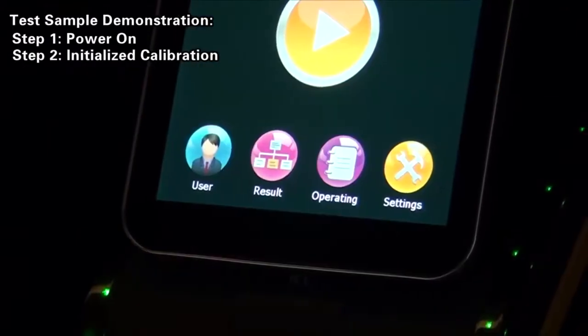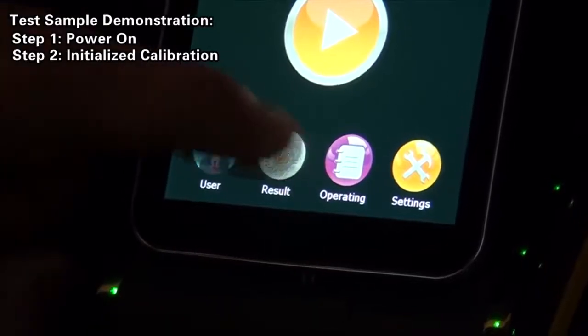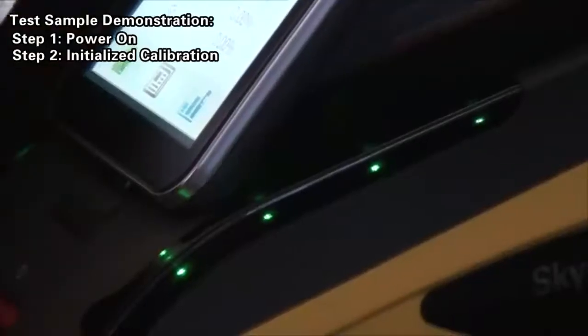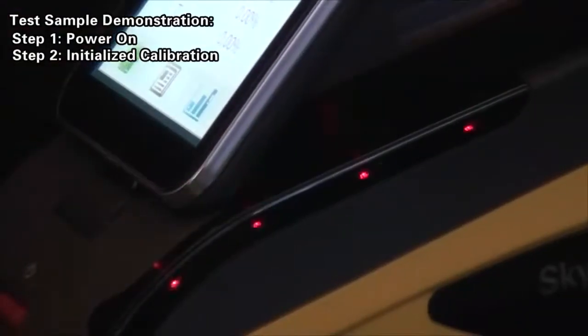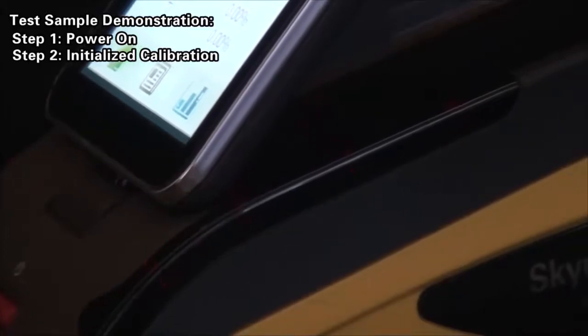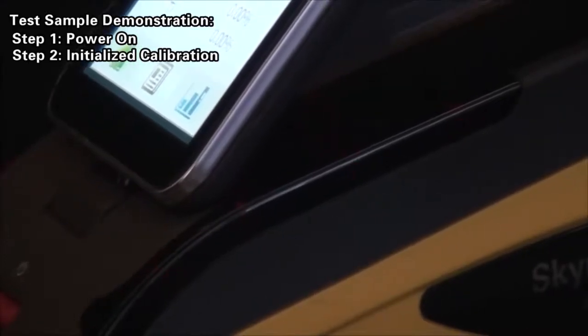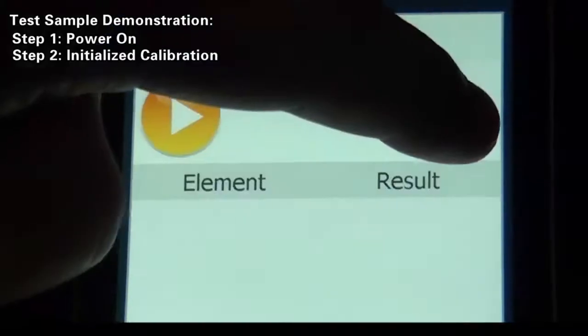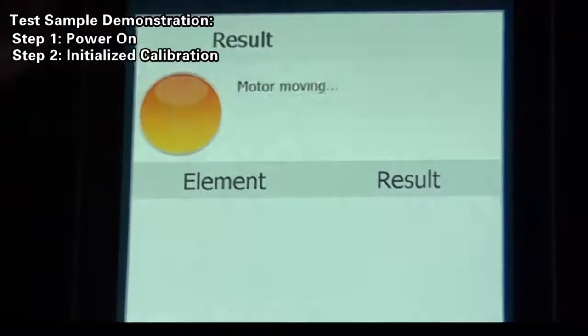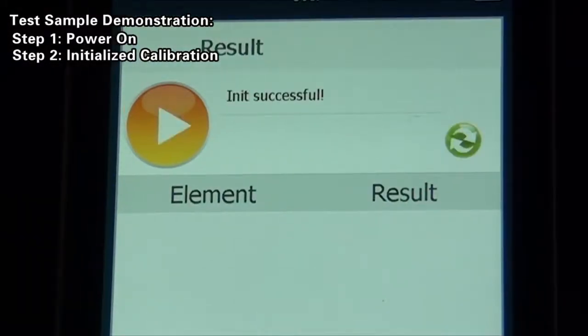On the main interface, click test results and go on to click the initialization button. The green colored instrument indicator light changes into red flashes and the instrument is being initialized. This process usually lasts over 10 seconds.